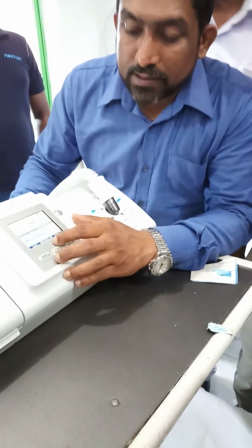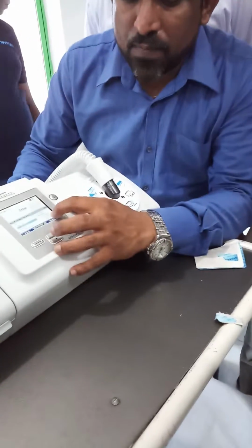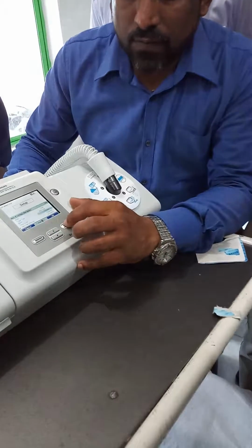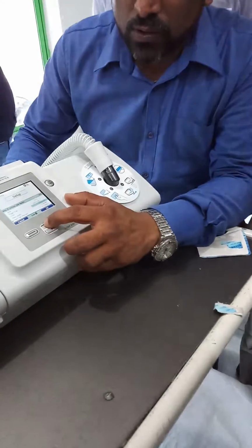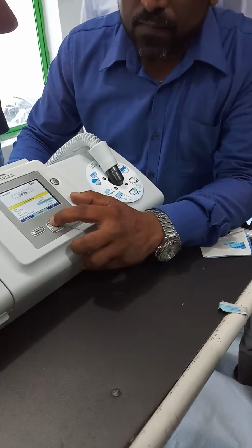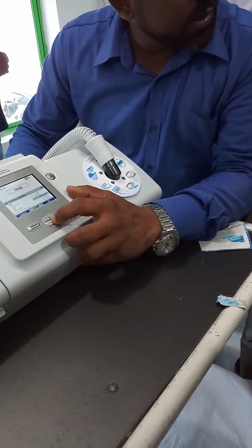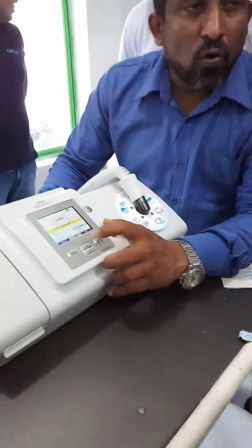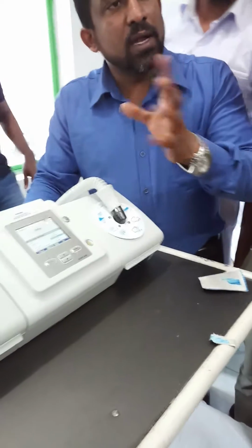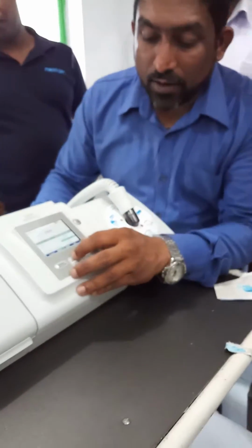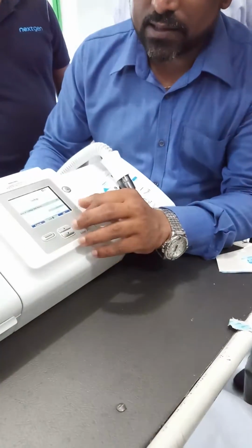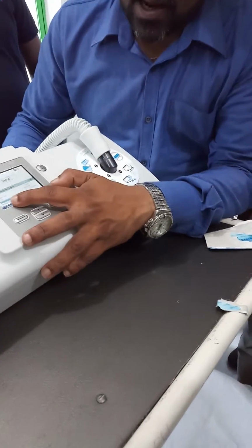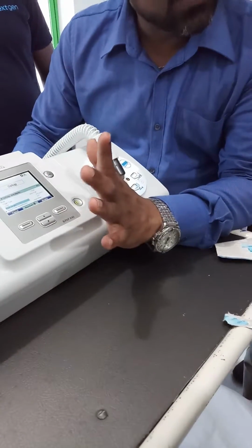Select the CPAP mode first. Auto track is the trigger, keep it on auto track, don't worry. This is the pressure. It goes up to 20, and the minimum is 4. Between 4 and 20 you can change the pressure, doctor. You fix the pressure and keep it like this. Ramp length is not needed, keep it off because this is CPAP.